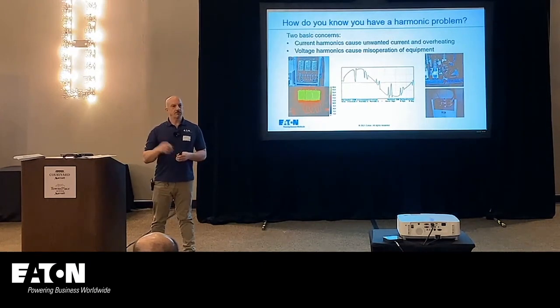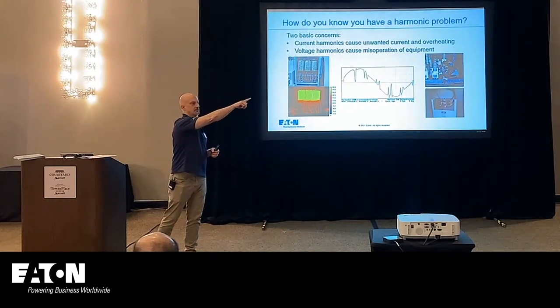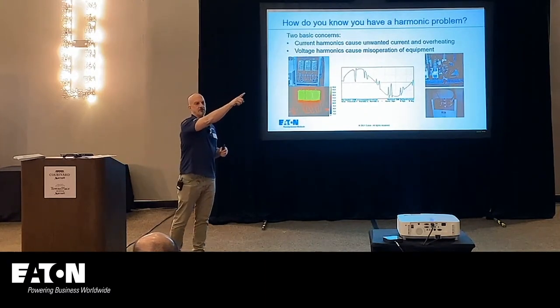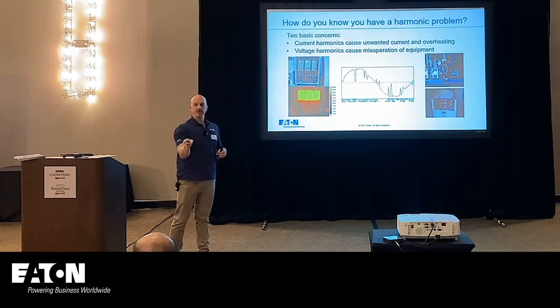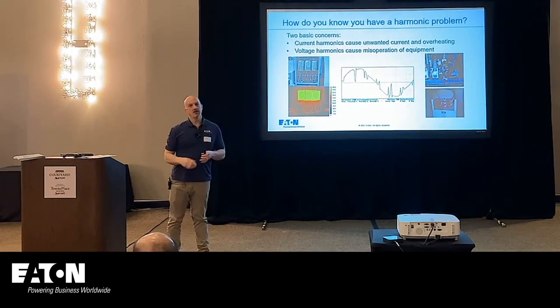Where does that 10 amps go? It flows out on one of the conductors. How many phases is a drive, typically? 3 phases, right? So it flows out on the conductor. Does it go to ground? Nope. It goes out on A, back on B and C. Just like normal current going into the drive, except it goes the other way, okay?